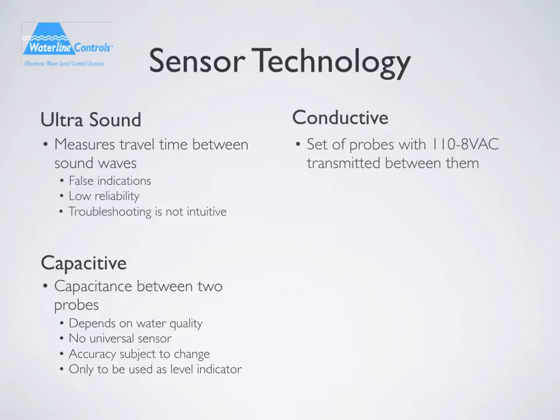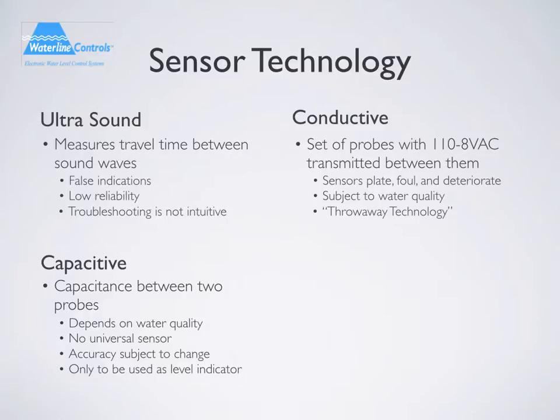Conductivity technology uses a set of metal probes with power transmitted between them, ranging between 110 volts AC to 8 volts AC. This method causes the probe tips to plate, foul, or deteriorate and are subject to water quality issues due to the electrical current transmitted between the probes. Some OEMs have termed this a throwaway technology due to poor reliability and performance. More importantly, no conductivity sensor has been listed by a nationally recognized testing laboratory such as UL, ETL, or FM.